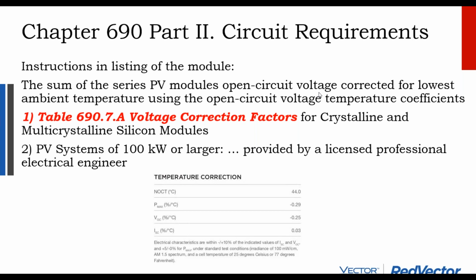Solar, we have additional temperature correction factors that are special for solar that get applied. And often these temperature correction factors are found right on the spec sheet of the module. Most solar modules are made out of silicon. Pretty much all solar modules that are going on a rooftop are made out of silicon. And even though you might have slight differences between a monosilicon panel or a polysilicon panel, we're really splitting hairs here. Silicon has similar characteristics regardless of the type of silicon used.